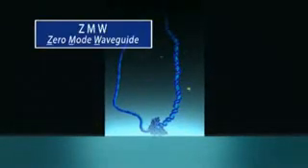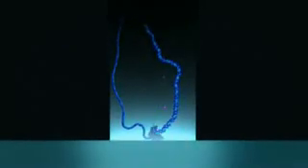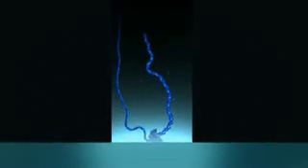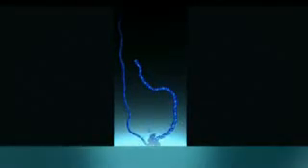The second key technology is a nanophotonic visualization chamber called the zero-mode waveguide, or ZMW. It enables observation of individual molecules against the required background of labeled nucleotides while maintaining high signal to noise. The ZMW is a cylindrical metallic chamber, approximately 70 nanometers wide, that is illuminated through its glass support, creating an extremely small detection volume, just 20 zeptoliters.